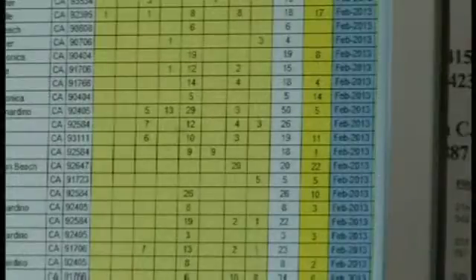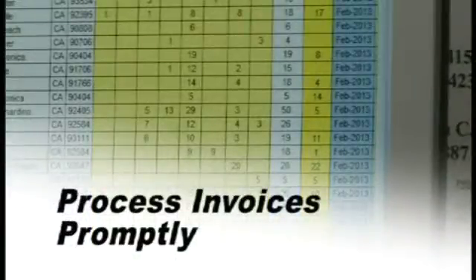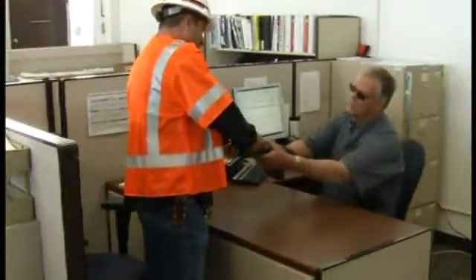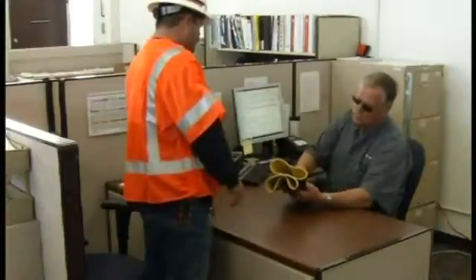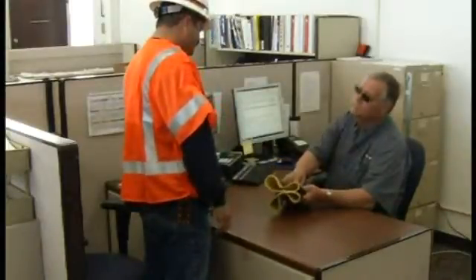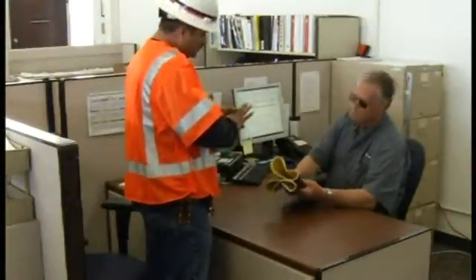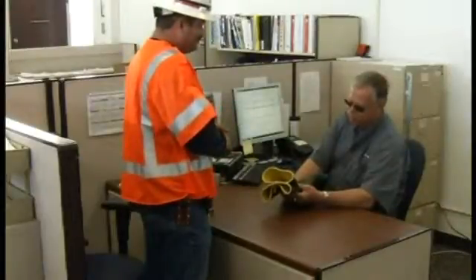The supervisor will only be charged for testing on all gloves that are returned and pass the retest. If they are not returned or fail the retest process, the supervisor will be charged for a new pair of insulating gloves. The supervisor must process the invoices for retesting and/or new glove replacement promptly upon receipt. It is important that your technicians understand how insulating gloves are to be tested, stored, and worn. More importantly, they must understand when they are to be used.